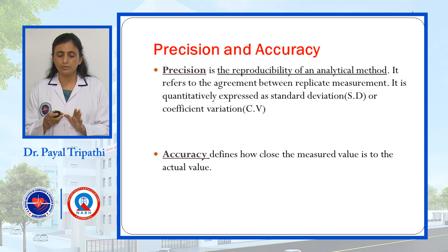Okay. Now, what is accuracy? There is a difference between precision and accuracy. Accuracy means if the known result, for example the sugar result, is 90, and our instrument gives a result of 90.1 or within an acceptable range up to 90.2, then it is accurate. If that instrument gives a result other than 90, like 180 or something, some observed variation, then it is not accurate in that particular test.